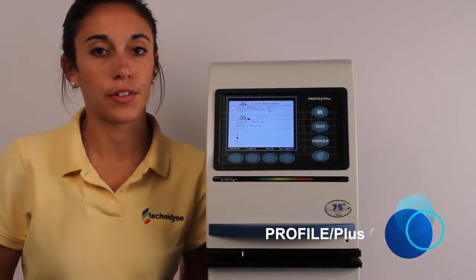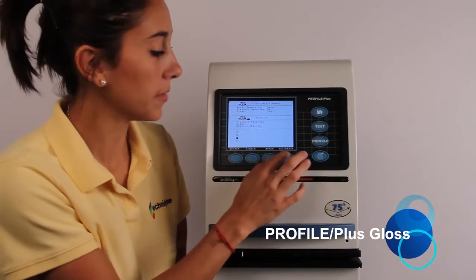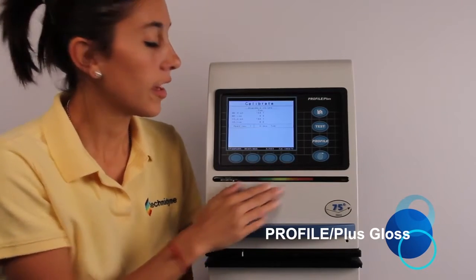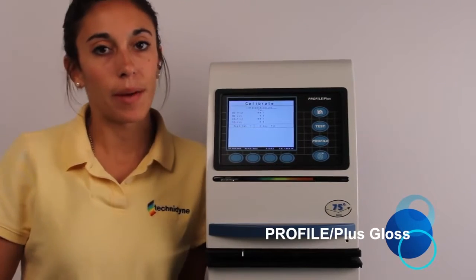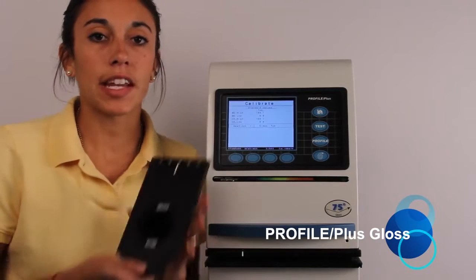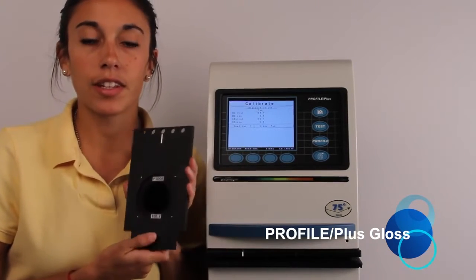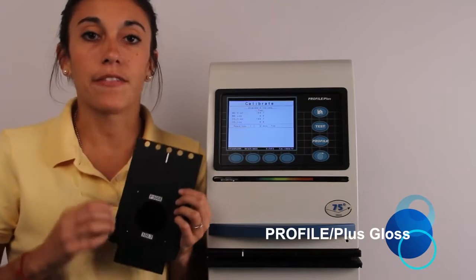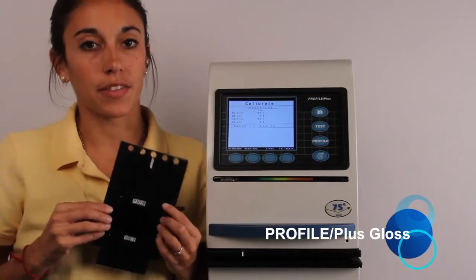Our first step for calibration, of course, is to press the Calibrate soft key. You should see that the value should be stored for the primary calibration. For this standard, our value is 100.7. This step brings the instrument back to factory calibration based on the values of the standard.